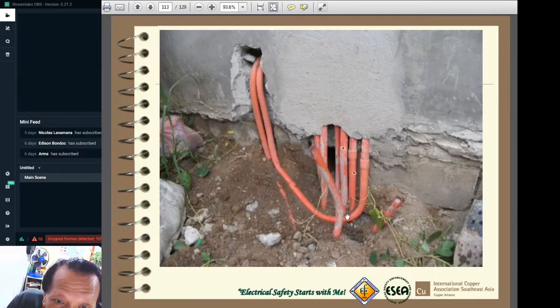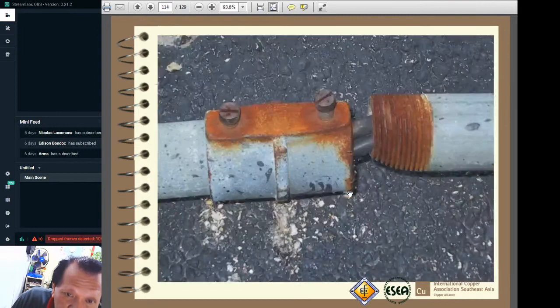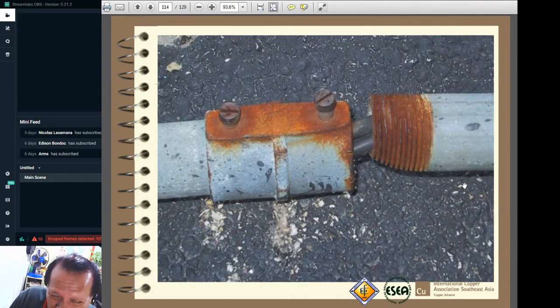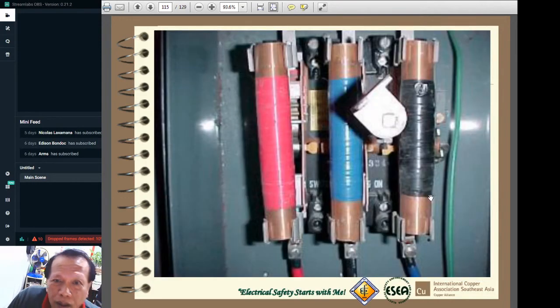Here, somebody was doing excavation works and hit the conduits. So here you could see holes on the conduit, thereby possibly exposing the one who is doing the demolition of the concrete by possibly touching the wires inside the conduit. Again, this one, the installer did not make it very firm, so that the connection of this coupling to the pipe would be very firm. And here is an improper use of the jumper. The person involved in the maintenance just simply used a copper tube as a fuse, which is incorrect. Therefore this installation doesn't provide any safety anymore to the load or to the feeder downstream.